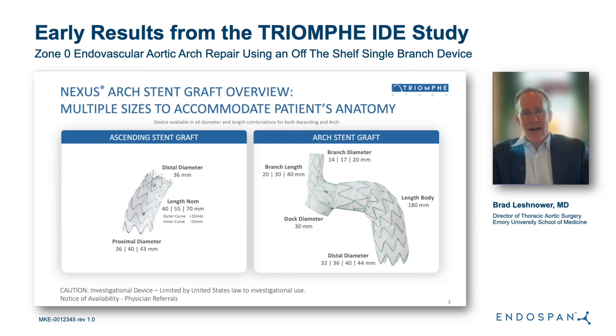The next component is a dock that is 30 millimeters in diameter, designed to be placed in the distal ascending aorta. The main body of the graft is 180 millimeters and comes in varying distal diameters ranging from 32 to 44 millimeters. The second component is an ascending stent graft that comes in varying lengths from 40 to 70 millimeters and varying proximal diameters of 36 to 43 millimeters, designed to fit most ascending aortic sizes.